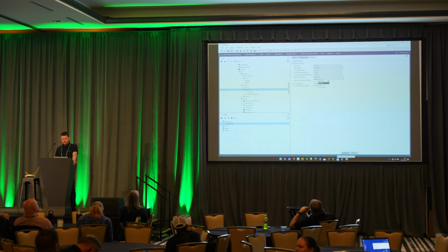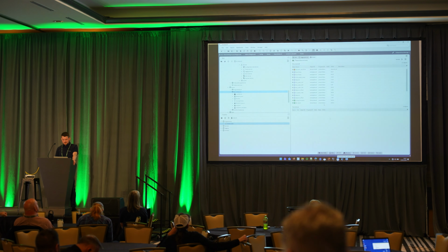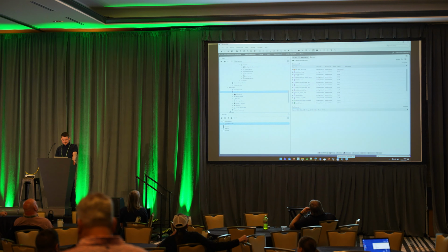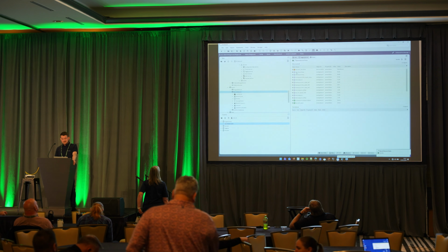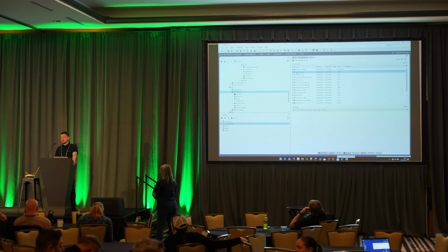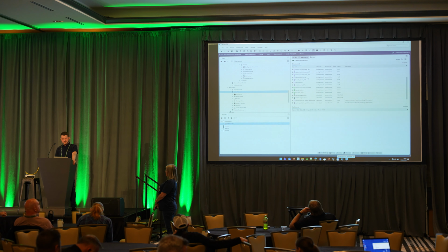When we change that mode to the double parent and save it, and we go back to our BACnet device in Niagara, and now we discover those points, it's using this equipment to name the points. So you can see now in the BACnet point exactly which VAV this room temperature is coming from. No linking, just one click, and all points are being applied on the fly as we speak.